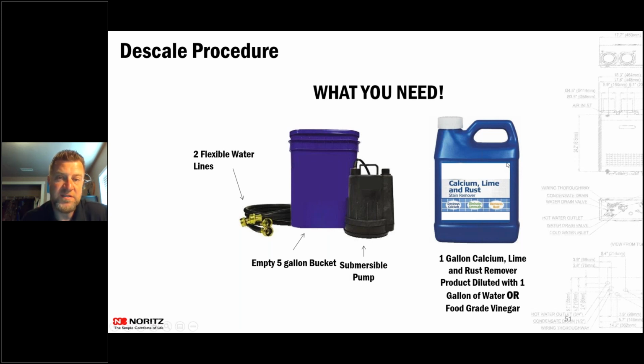If you've got an older unit that hasn't been flushed in 3, 4, 5, 6 years, using a calcium lime rust remover or something more aggressive will work better on units that haven't been flushed in a long time. But typically, if you're doing the maintenance on a tankless water heater and flushing it every year, that food grade vinegar should work just fine.